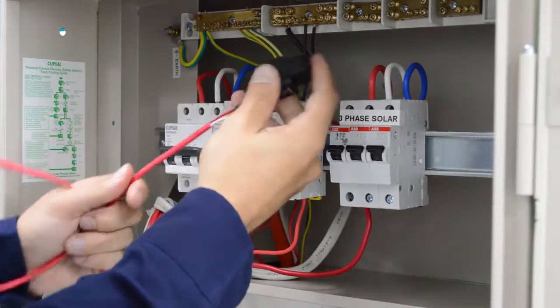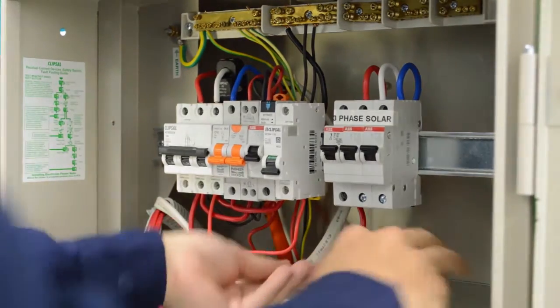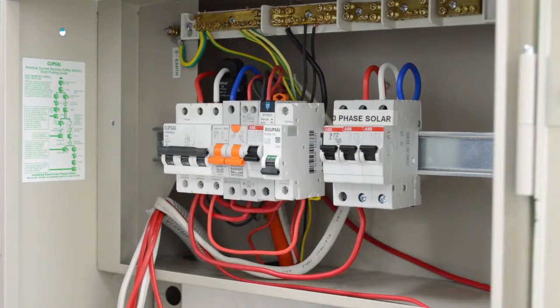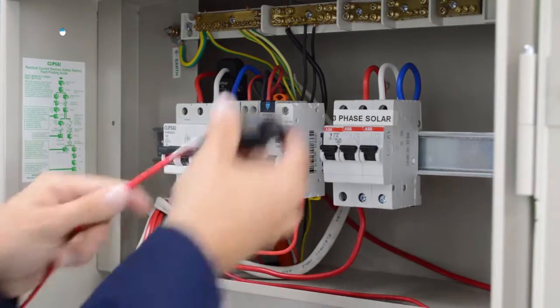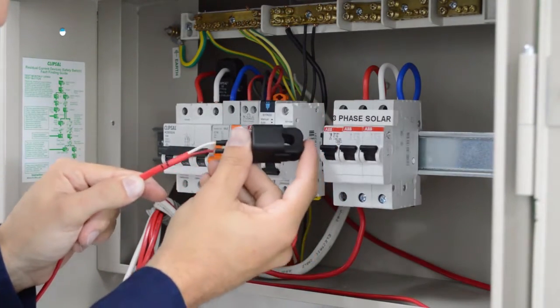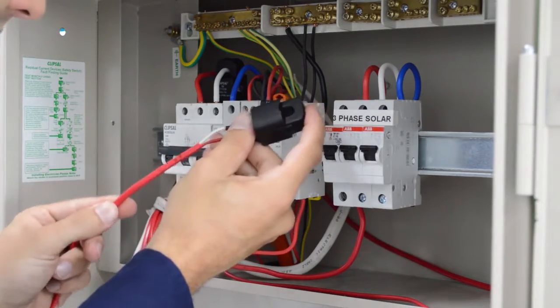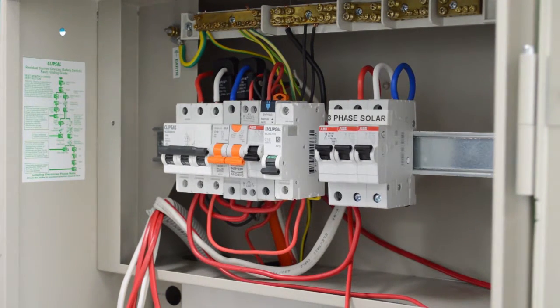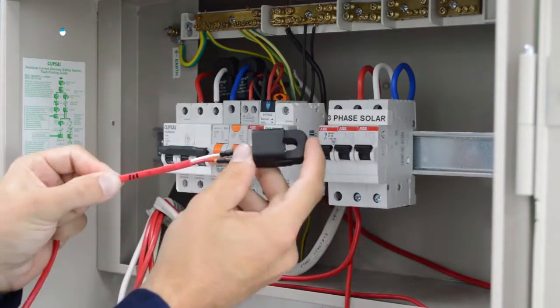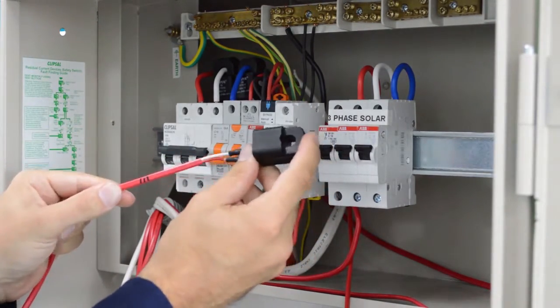You can now clamp the mains active clamps around the main actives, starting with the same phase the unit is powered from. So in this case, I've powered off the lighting circuit, which I previously determined is connected to white phase. So it is important that I connect current clamp number 1 around the white phase. I can now connect the second current clamp around the next phase in the phase rotation sequence, which we're taking as standard. Therefore, the second current clamp will be clamped around the blue phase. I'm now going to connect the last current clamp onto the last phase available, which is the red phase.